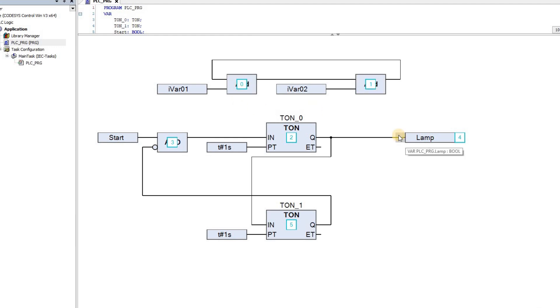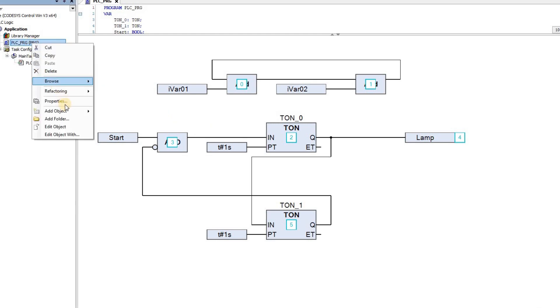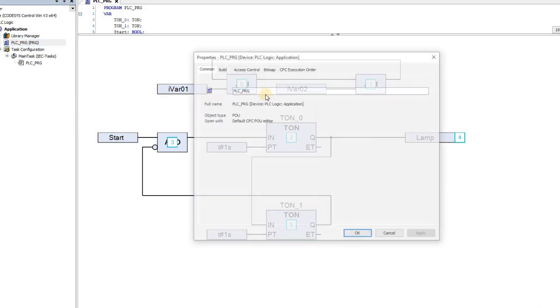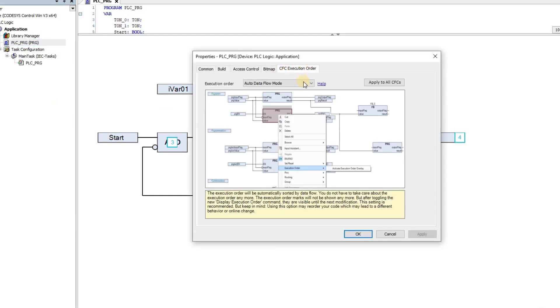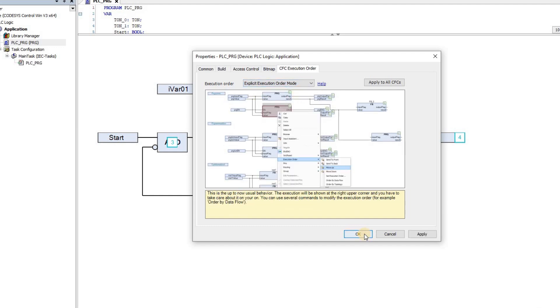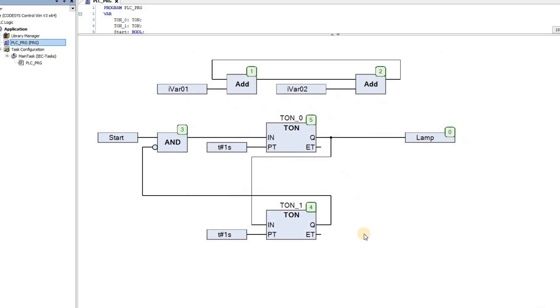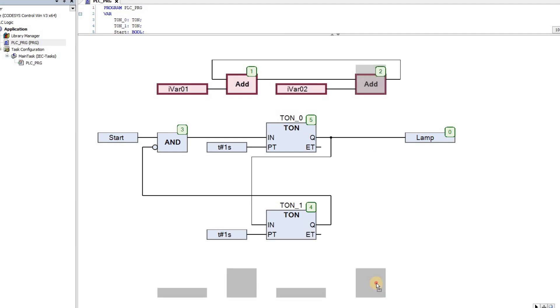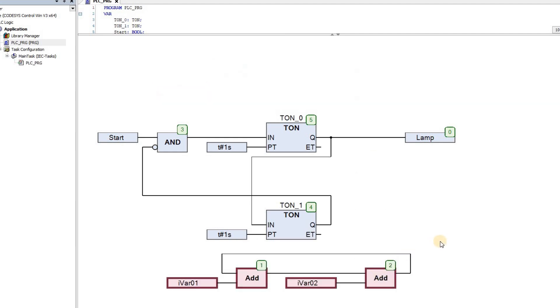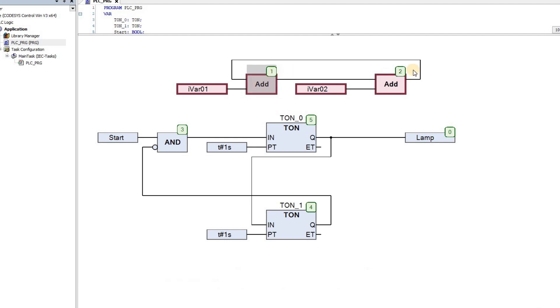The second mode for determining the execution order is called Explicit Execution Order mode. You can choose this option by right-clicking on the POU, choosing the Properties, CFC Execution Order, and then in the execution order, you can choose this Explicit Execution Order mode, and then click on OK. Then the execution order for all blocks in the editor will be shown permanently. In this case, changing the topology of the networks will not change the execution order. So if I move this network downwards or upwards again, you see that the execution order is not updated. It doesn't change.